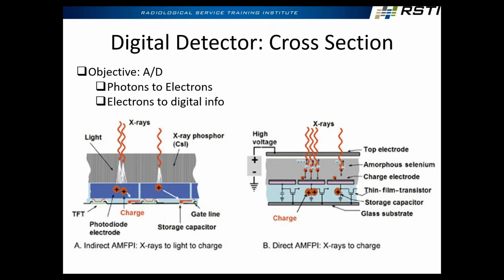And what the direct detector does is it converts X-rays directly to what? Electrons. So the Hologic's mammo product is called the Selenia Dimensions. Selenium is an element that occurs in nature. And if you look up selenium, it's a photoconductor. It conducts with photons. In other words, when photons strike selenium, it gives up a charge. So now I have electrons floating around in this layer of selenium proportional to the photons that struck it up here.